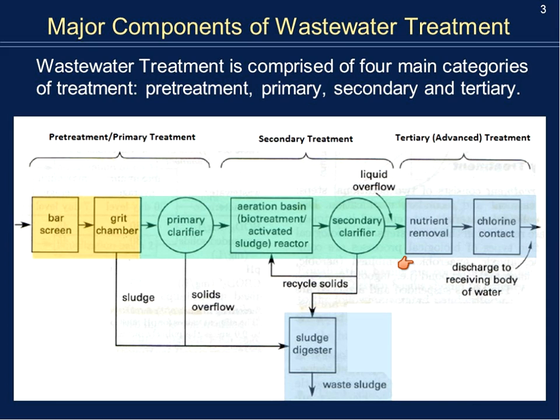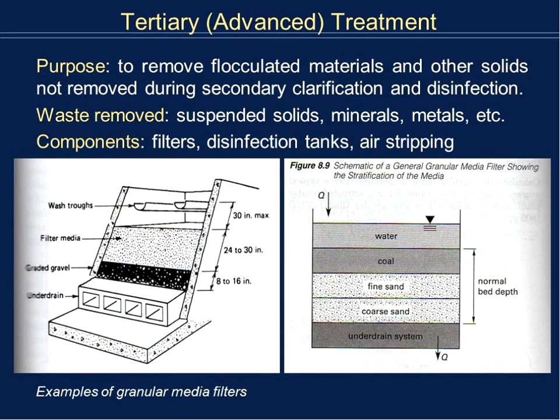Today we're going to look at tertiary, or the third type of treatment, which we often call advanced treatment because not everybody uses it. We'll look at items such as nutrient removal and chlorine contact for disinfection. We're also going to talk about the sludge digester — what happens to all of that solid material that we remove. The main purpose of tertiary treatment is to remove any material not removed so far, typically through another clarification and disinfection. What we remove are suspended solids, minerals, and metals — much more fine material at the molecular level. Major components are filters, disinfection tanks, and air stripping, which removes gases we don't want in the system.